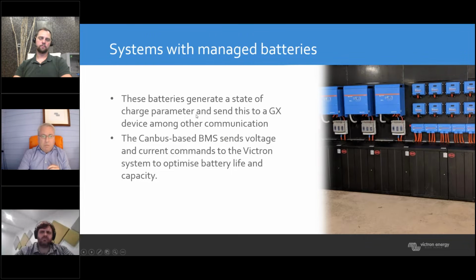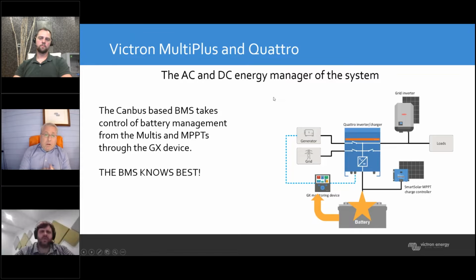It's a slightly different way of allowing the proper charge to happen to these batteries. In any battery situation, the BMS knows best about what should be happening with the batteries. It knows what current should be going in at any one time, what voltages the cells should be seeing, and what the maximum discharge rate of the cells is at any one moment. So to facilitate this, we give over control of the inverter charger, not just charging but also discharging, to the BMS itself. In the end, you get coordinated communication that allows the batteries to perform to their maximum potential, to last the longest, and to have a smoothly running system that gets everything out of it that you're hoping to achieve.